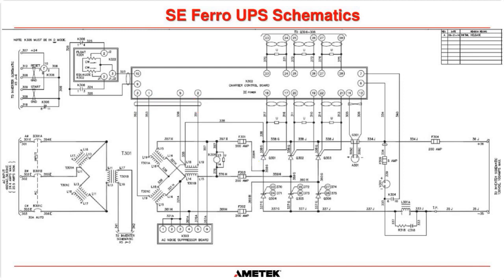Out here we have our float and equalize pots, and when I say out here, they're usually mounted on the inside of the system to the right hand side. They're not mounted on the charger control board. They're separate. They're usually 2 stainless steel potentiometer knobs. One is for float and one is for equalize.